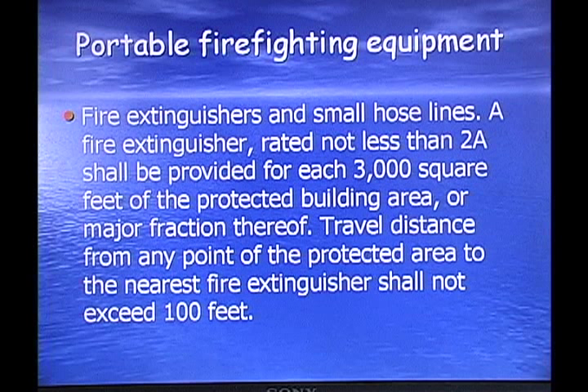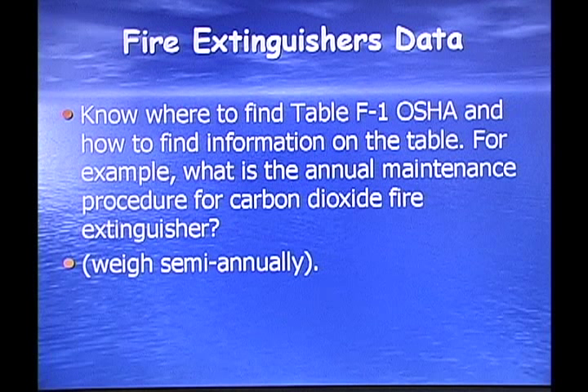Firefighting equipment — fire extinguishers and small hose lines: a fire extinguisher rated not less than 2A shall be provided for each 3,000 square feet of the protected building area or major fraction thereof. Travel distance from any point of the protected area to the nearest fire extinguisher shall not exceed 100 feet. You need to know where to find Table F1 in your OSHA book. For example, the annual maintenance procedure for a carbon dioxide fire extinguisher is that it needs to be weighed semi-annually.